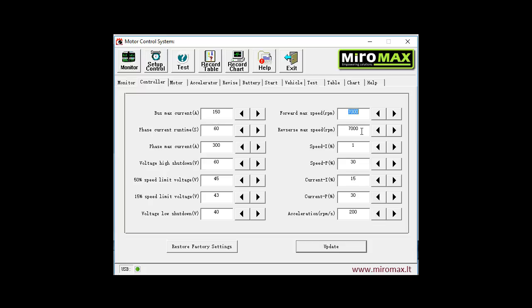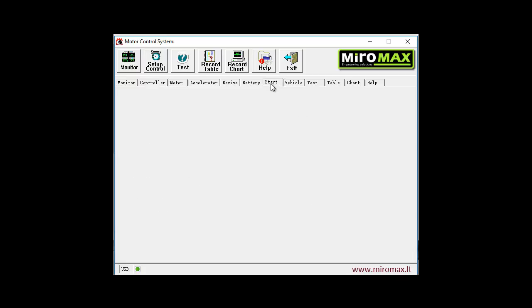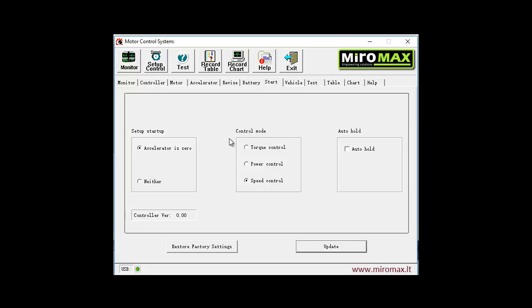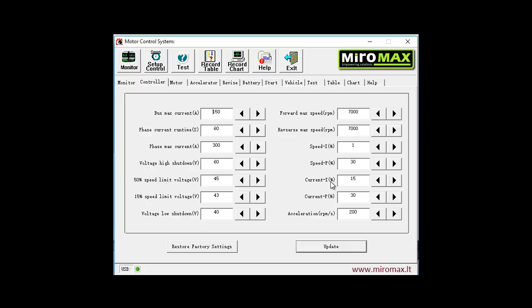On the right side we see maximum settings for turning speed, for RPMs respectively for forward and reverse direction. And then we see four parameters related to motor control dynamics - they are feedback parameters that are used to control motor behavior in time. They are related to motor control mode which we have mentioned previously, and depending on what control mode you use, you may need to change these parameters. And finally, acceleration rate expressed in RPMs per second.